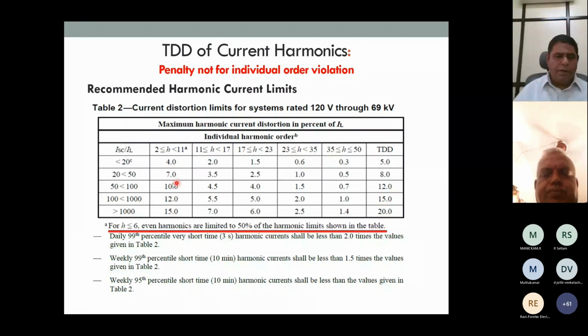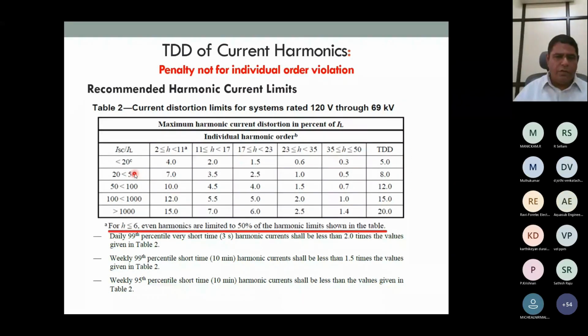Likewise, if the short circuit ratio is, for example, 35, then the limit will be 8%. If the short circuit ratio is higher, say for example 150, 15 will be the limit. So how is this short circuit ratio arrived at? It's a bit simpler, and empirically it is said, the farther away from the EB substation, you will get a very tight limit. The one who is very close to the substation will get a 20% limit. Someone in between will get around 12%, and the one at the tail end, almost the last consumer in that circuit, will get a very stringent limit of 5.